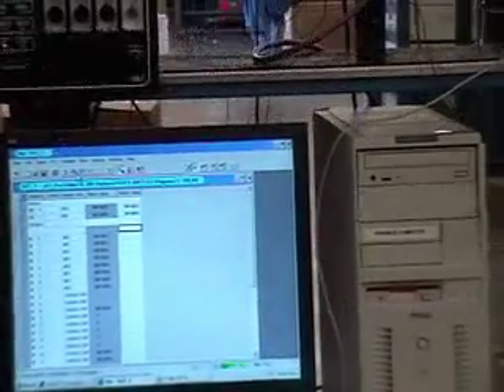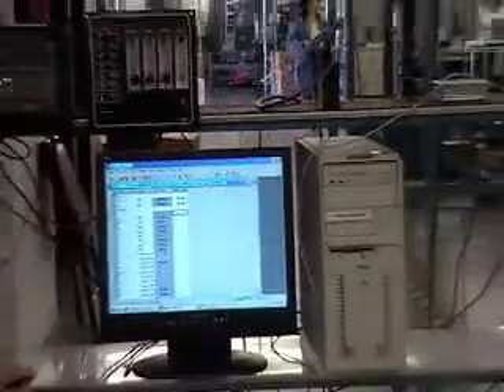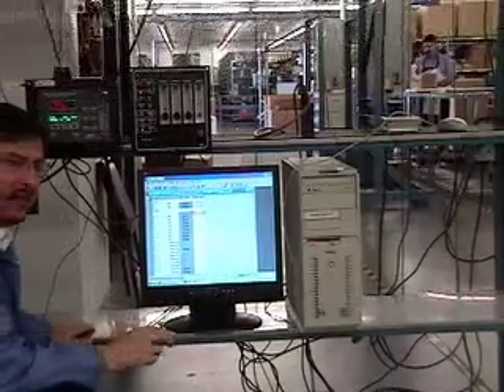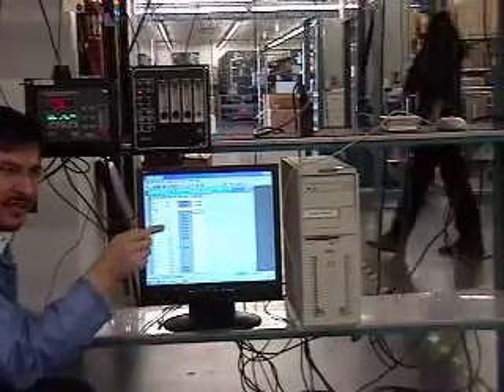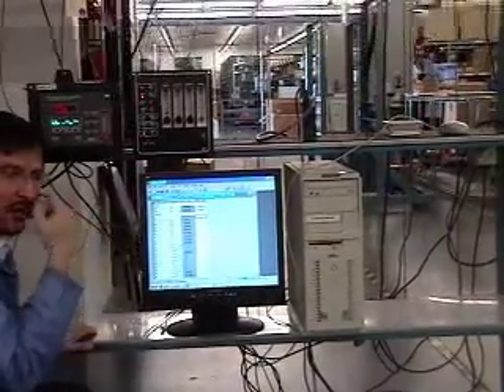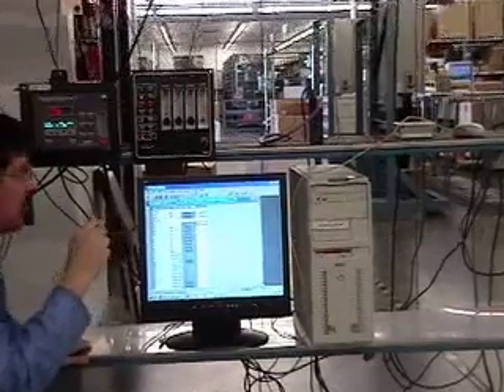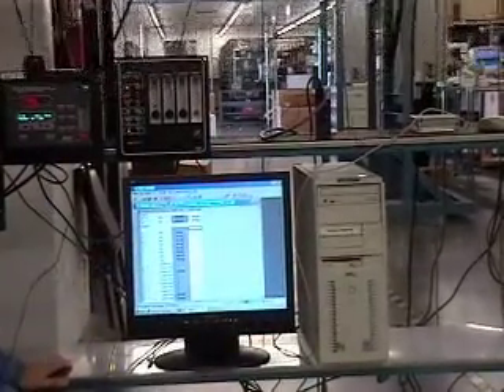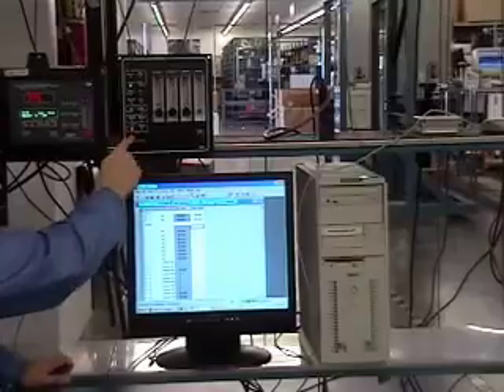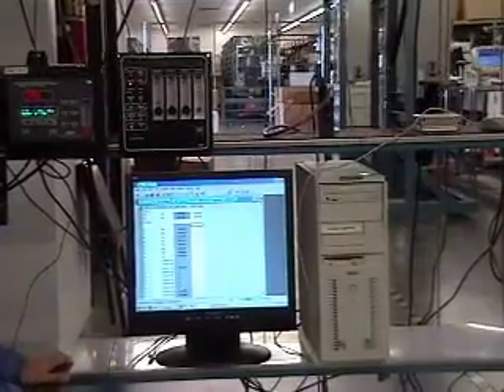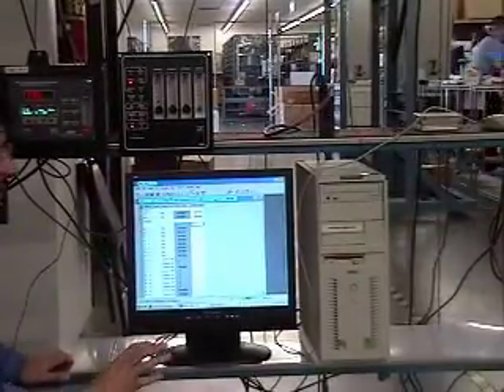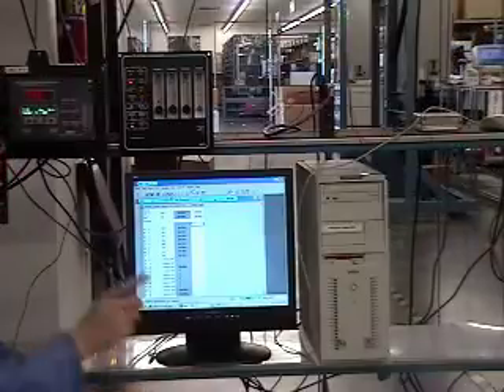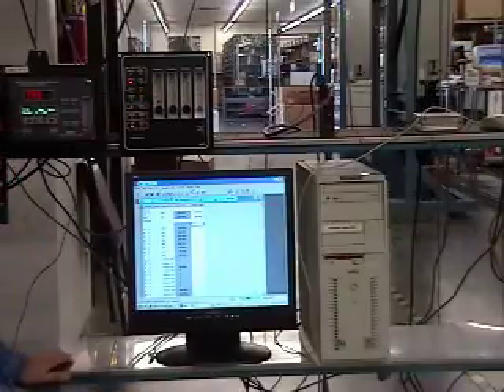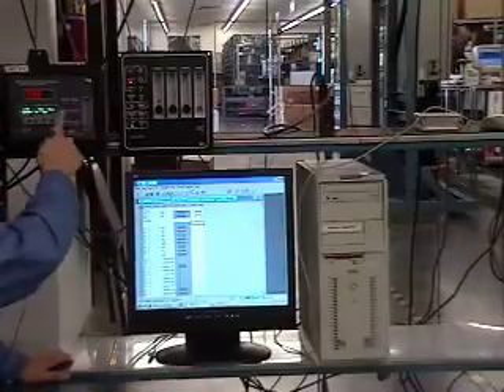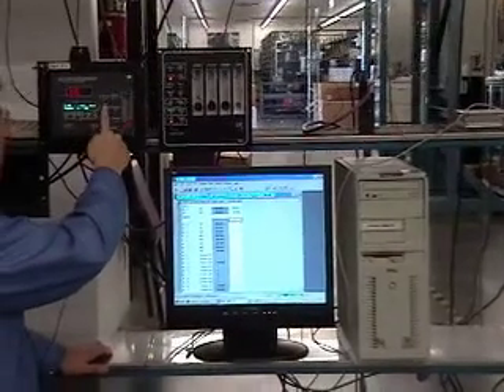So now I want to send some commands. You can do it through the back, through the 15-pin connector on the back. You can check the manual for which pins you gotta short to ground so that you can control the valves on the front. Right now, it's still under the PLC control. So it's not quite there in computer control. But it's under analyzer control.